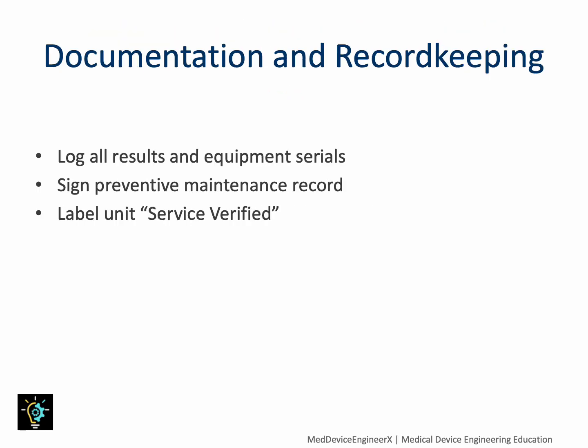After all tests pass, complete the service record. Include serial numbers, technician signatures, calibration references, and measured values. A proper record demonstrates compliance and accountability. Once verified, attach a service verified label with inspection date. This documentation is more than formality. It ensures traceability and provides confidence that the FT10 meets operational standards for clinical use.